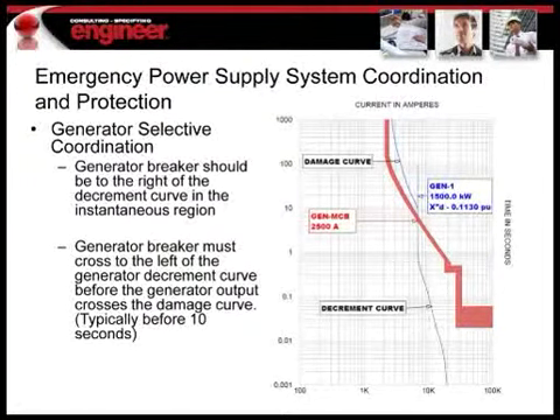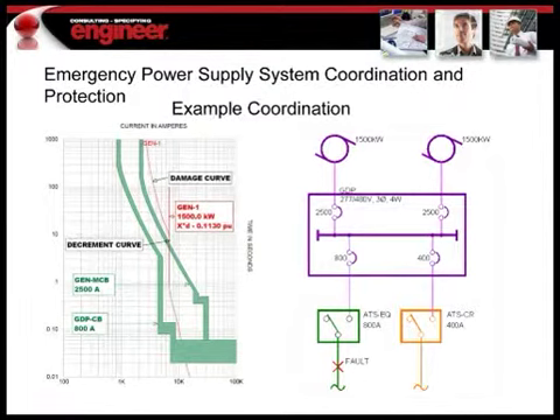Now we're going to add in a breaker. So here's our example situation where we had an 800 amp breaker on ATS EQ, and this was a fault. And we want to make sure that that fault is picked up by the 800 amp breaker before it gets to the 2500 amp. So you can see in this curve, the leftmost curve is an 800 amp breaker that serves the equipment branch. It's on the left side of the decrement curve the whole time, that 800 amp breaker, and it always will react before the generator breaker. But for whatever reason, if that breaker didn't work and didn't react, that generator breaker would actually be there to protect the generator before it got damaged. So that's pretty much it in a nutshell to protect generators.